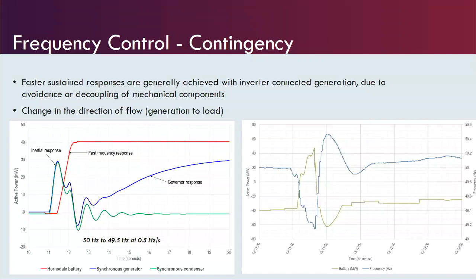The red is basically what we'd call a fast frequency response. Being an inverter system, it doesn't provide any inertial response, and that's probably one of the main drawbacks of inverter systems - not just batteries, but wind farms and solar farms as well. So you don't get any initial response, but a few seconds after the event, it can ramp up really quickly, pretty much to full output.